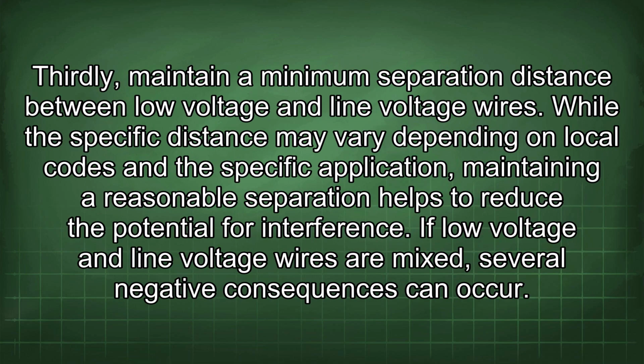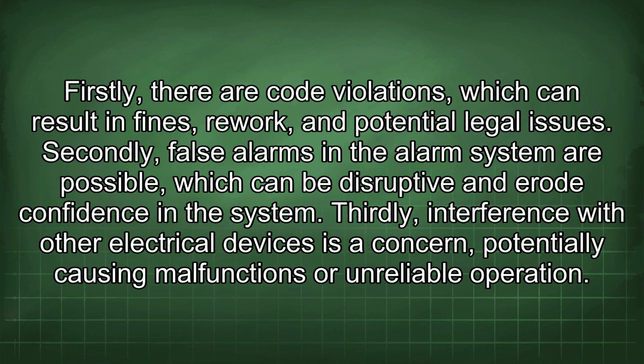Thirdly, maintain a minimum separation distance between low-voltage and line-voltage wires. While the specific distance may vary depending on local codes and the specific application, maintaining a reasonable separation helps to reduce the potential for interference. If low voltage and line voltage wires are mixed, several negative consequences can occur. Firstly, there are code violations, which can result in fines, rework, and potential legal issues.